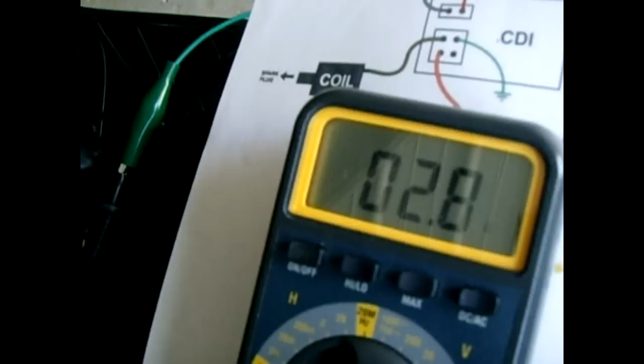I'm going to touch it to the black and yellow wires and let it stabilize. I get a reading of 2.8, which is really about 2 ohms after deducting the wire resistance. So if I checked this coil right at the back of the coil, it would give me around 1.9 to maybe 2 ohms, which is perfect. You want to be under 3 ohms, but over about 0.8.